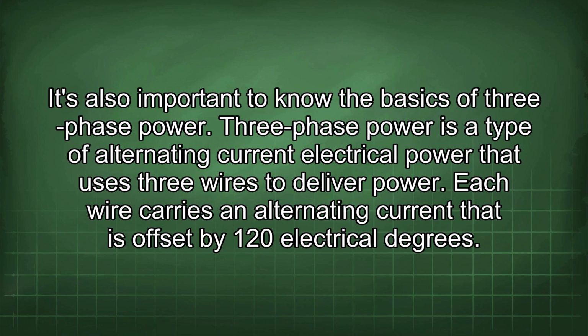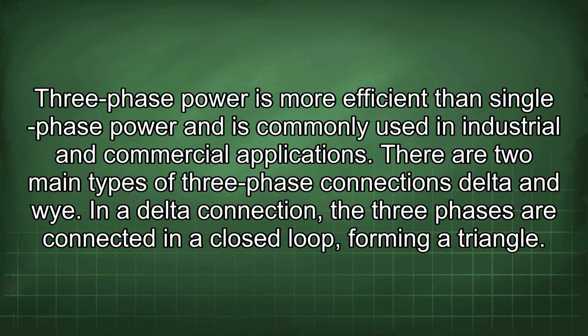Three-phase power is a type of alternating current electrical power that uses three wires to deliver power. Each wire carries an alternating current that is offset by 120 electrical degrees. Three-phase power is more efficient than single-phase power and is commonly used in industrial and commercial applications. There are two main types of three-phase connections, delta and Y.